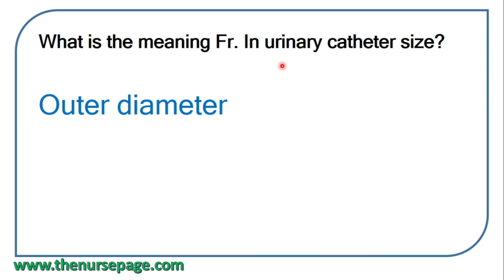1 French equals 1/3 millimeter, so 1 millimeter equals 3 French. Therefore, a 14 French catheter has an outer diameter of 14/3 = 4.66 millimeters.